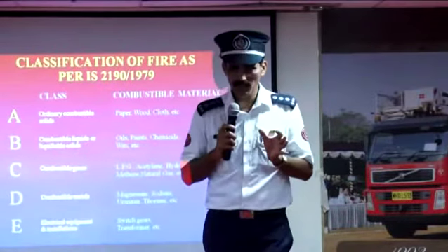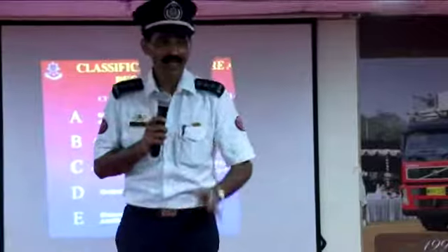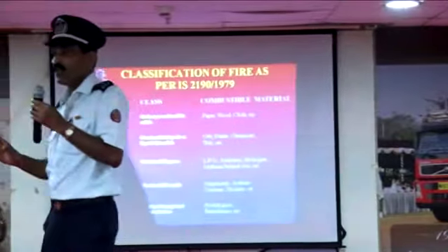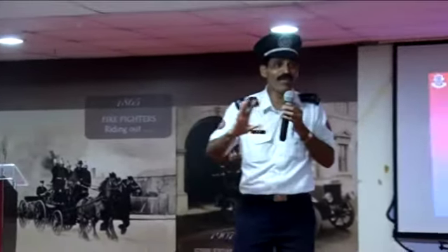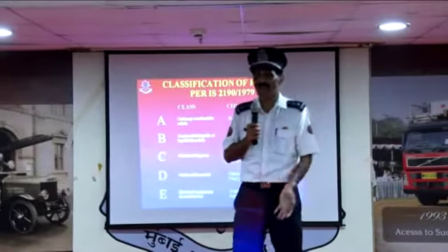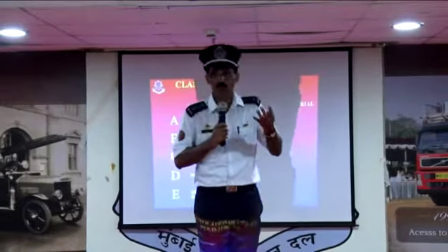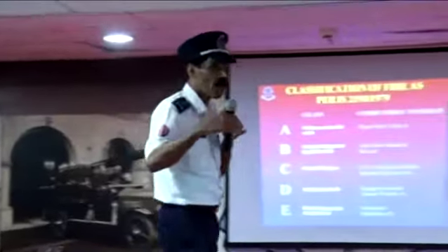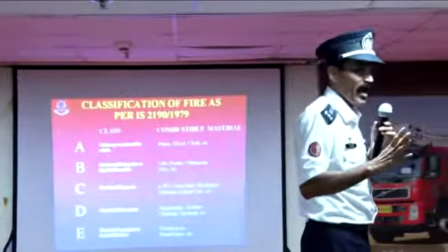So the second exception is the solid burning substances on which, on application of water, the intensity of fire will be increased, not decreased. Okay. Some combustible metals, or what we say light metals: sodium, potassium, magnesium, uranium, thorium, like radioactive metals. When these metals are burning, they burn at very high temperature, above 1600 degrees centigrade, and water has a bad property.